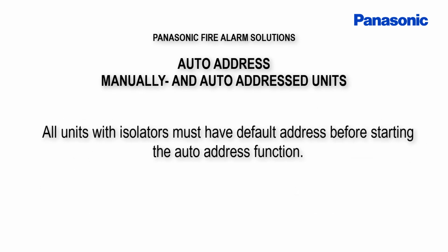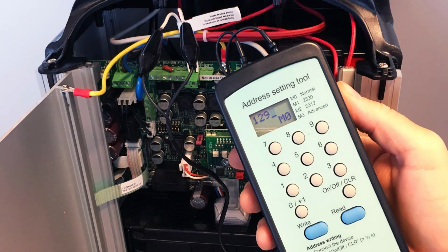All units with isolators must have default address before starting the auto-address function. For a unit without isolator and without base, we must set the address manually. Connect all units to the COM loop when the address has been set.